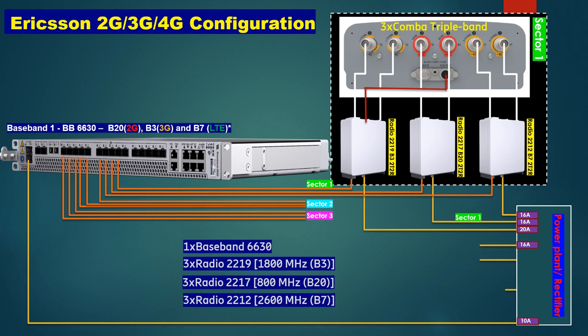We are using 14-ampere MCB for Radio 2212 B7 (2600 MHz) and 14-ampere MCB for Radio 2217 B20 (800 MHz). For Radio 2219 (1800 MHz) we are using a 20-ampere MCB. These are the Ericsson standard MCB ratings for these radios.